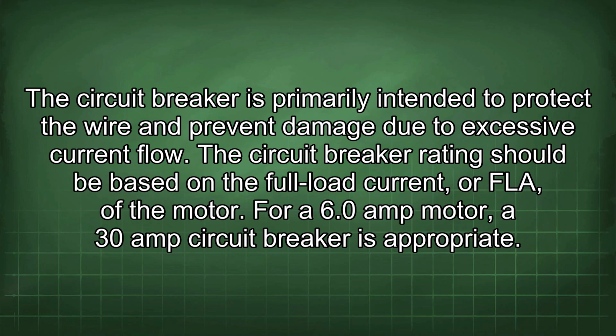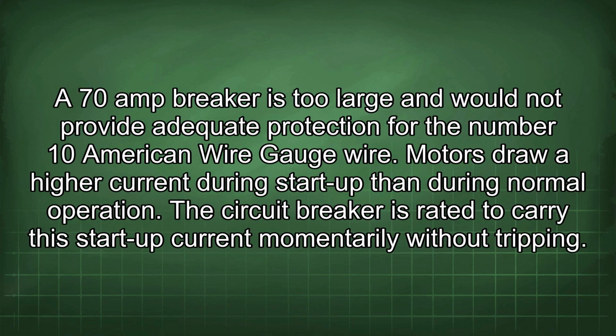The circuit breaker is primarily intended to protect the wire and prevent damage due to excessive current flow. The circuit breaker rating should be based on the full load current, or FLA, of the motor. For a 6.0 amp motor, a 30 amp circuit breaker is appropriate.